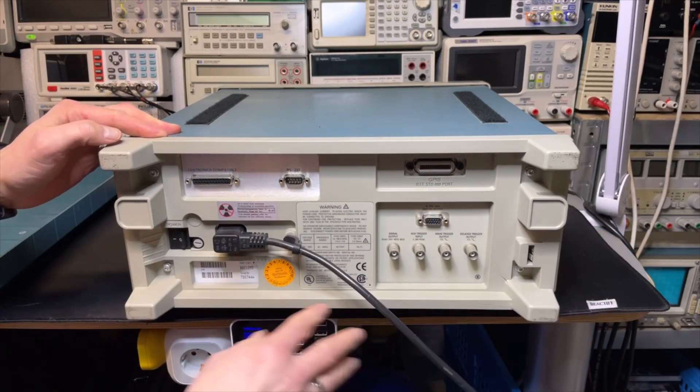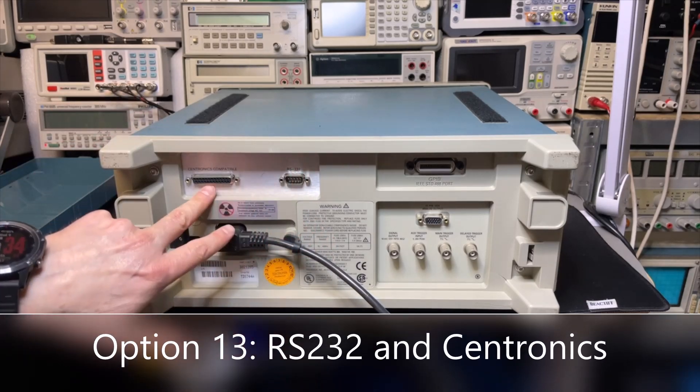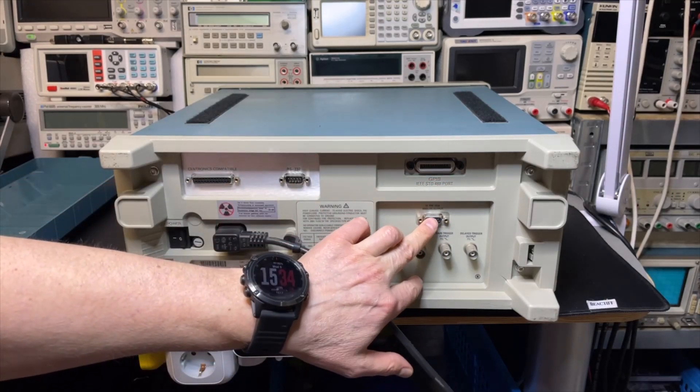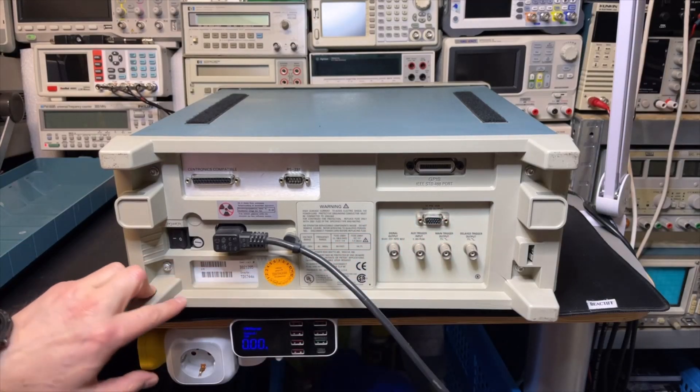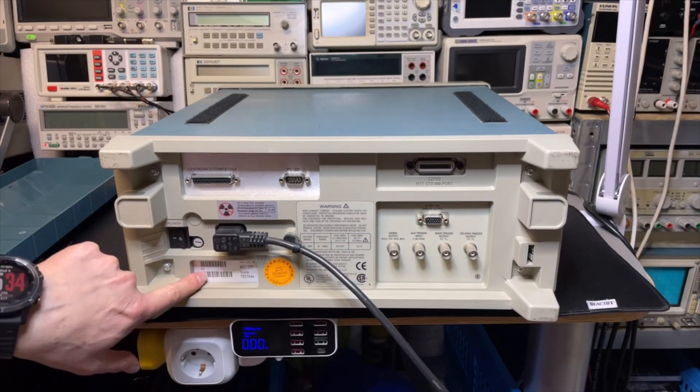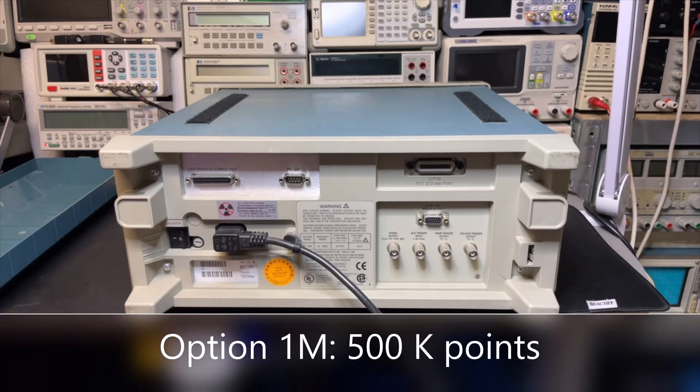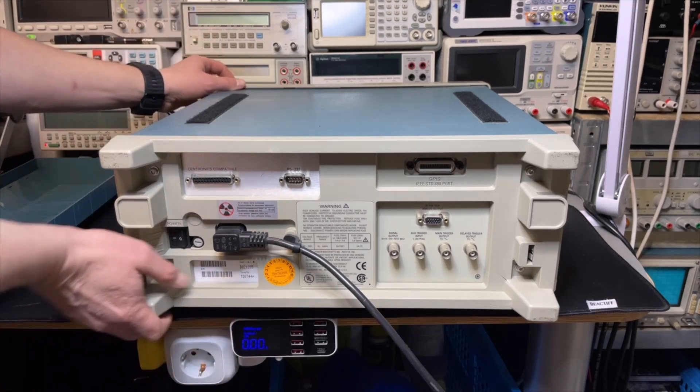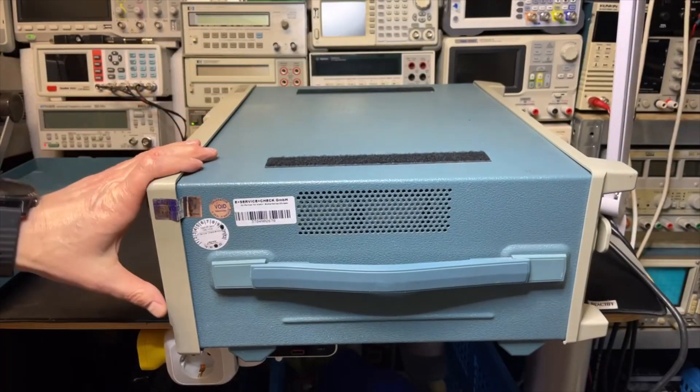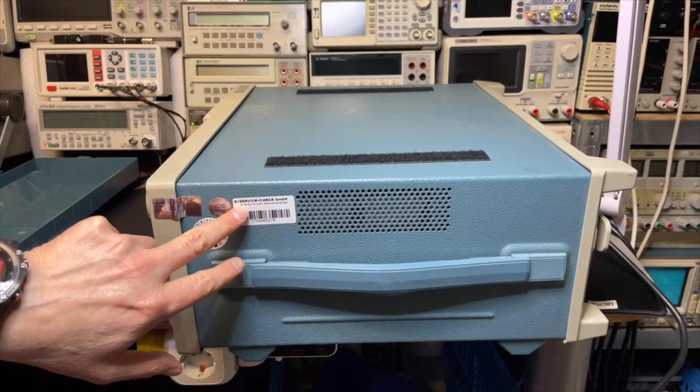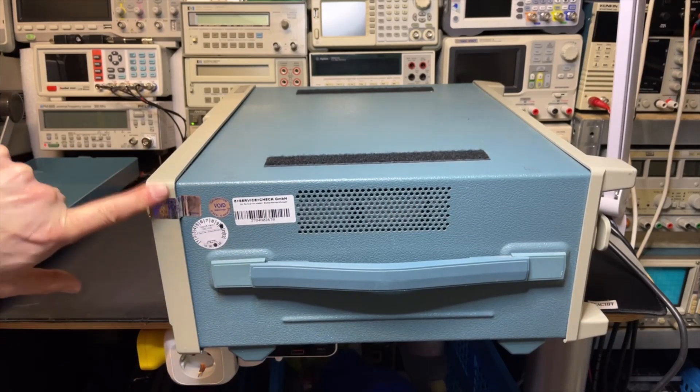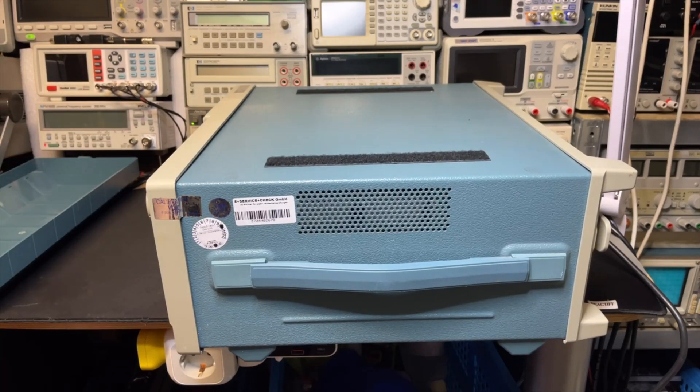It has a GPIB port, which is great, and even has VGA output. The serial number and instrument info show 1M, which could be one of the options installed. It was serviced in Germany in October, and the seal is still on it, so there's a big chance it's perfectly good.